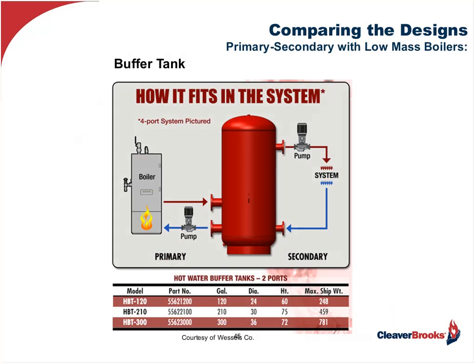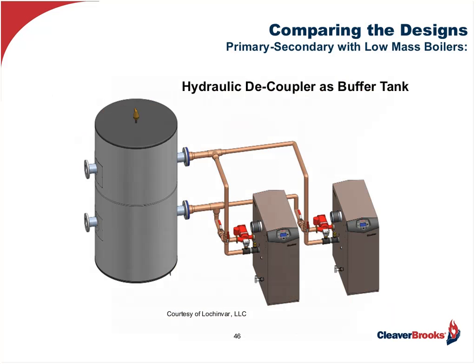Now the buffer tank is something that's needed. Here's a typical buffer tank. This is from a Wessel's catalog. You can see how it fits into the system. It just has 4 pipes. In this case, this is actually one that's used as a decoupler. And here's another example, actually out of an O&M manual for a low-mass boiler manufacturer. And you can see they're using the buffer tank as a decoupler as well.